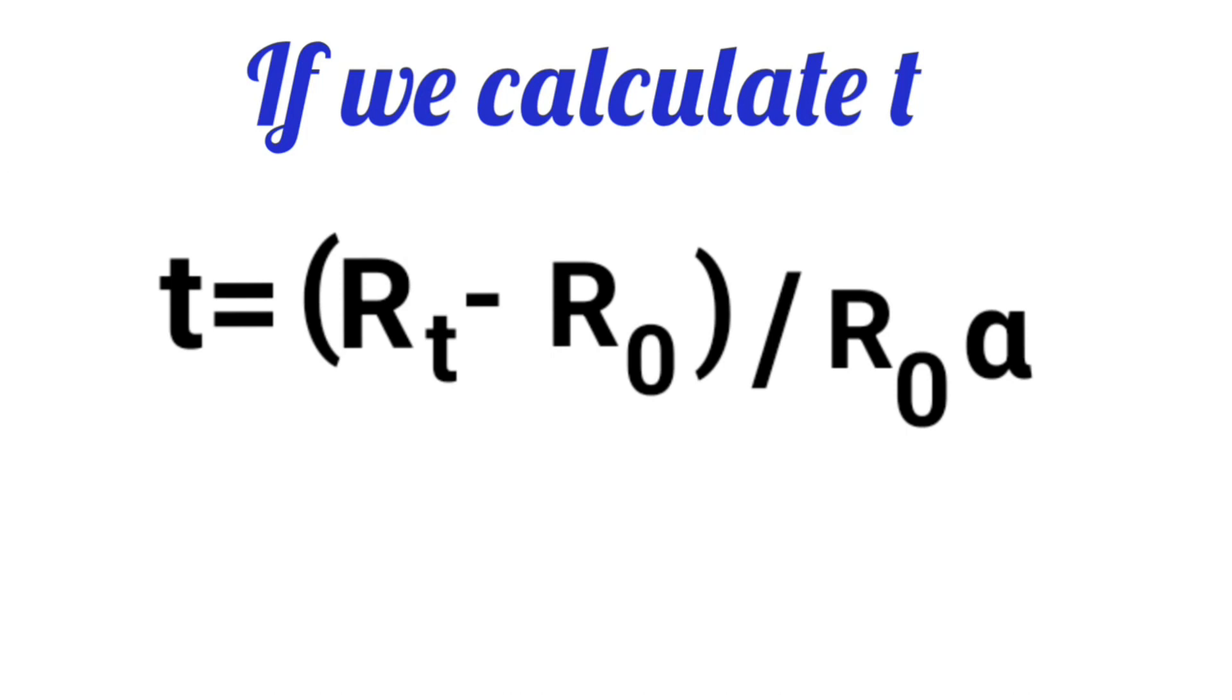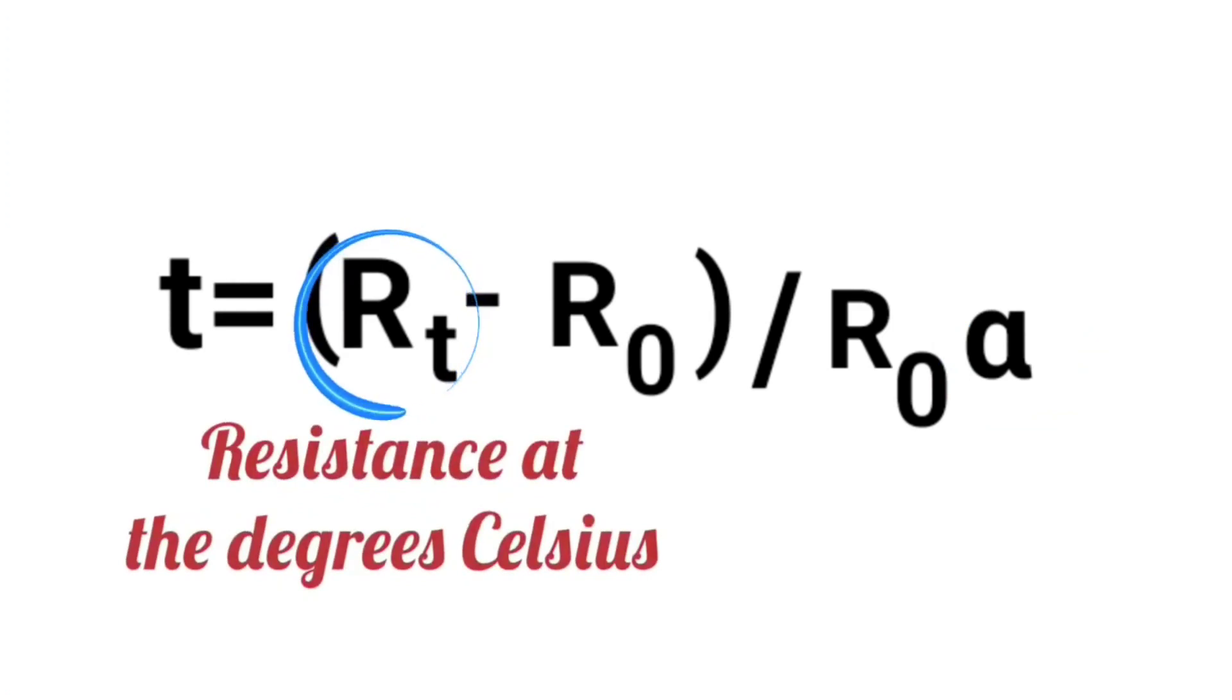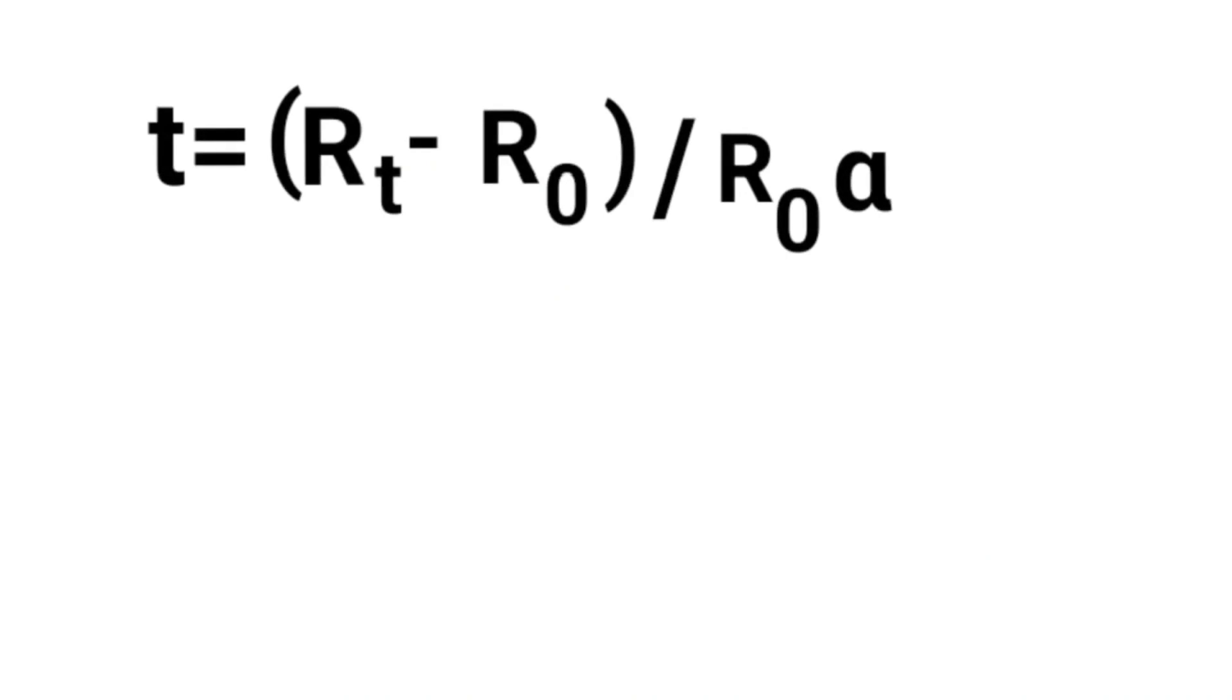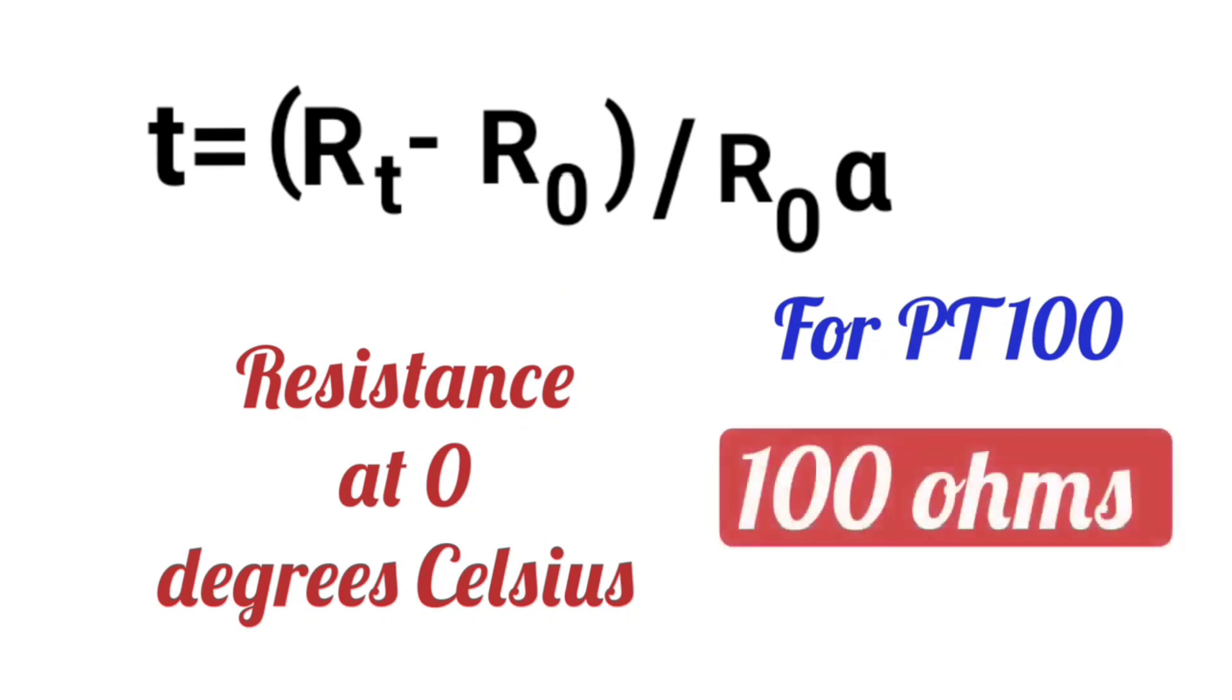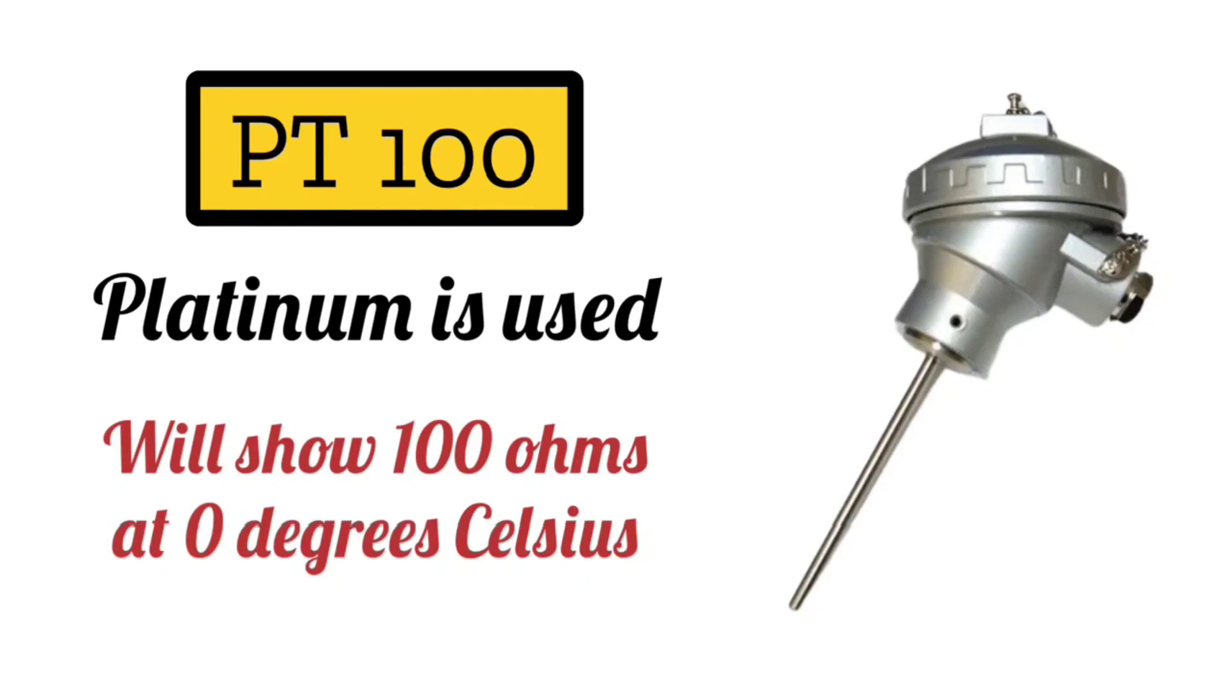Here you will see three parameters: RT, R0, and alpha. You need to calculate T. RT is the resistance at T degrees Celsius. Or understand it in this way, the resistance measured with a multimeter is RT. R0 is the resistance at 0 degrees Celsius. For PT100, the value of R0 is 100 ohms. PT100 means it's platinum RTD, and it will show 100 ohms at 0 degrees Celsius.